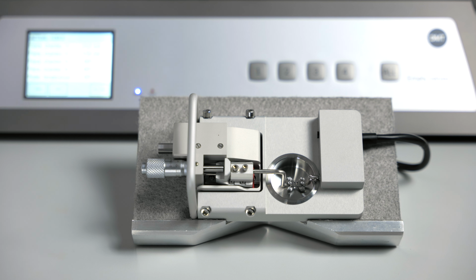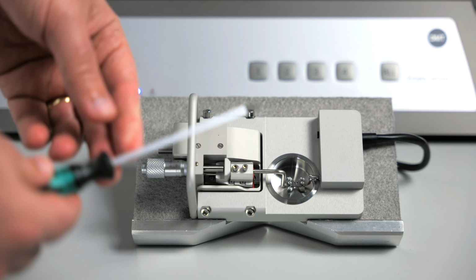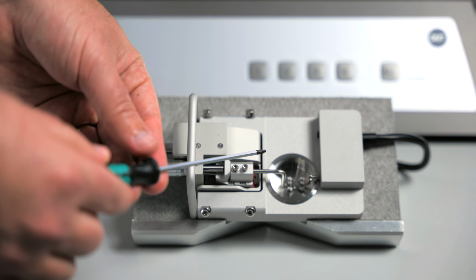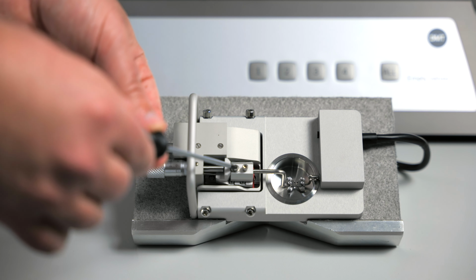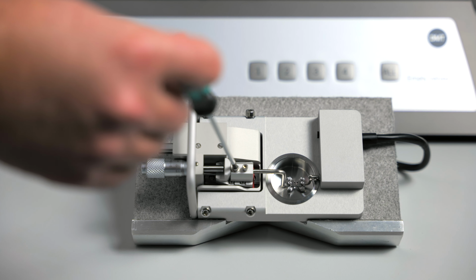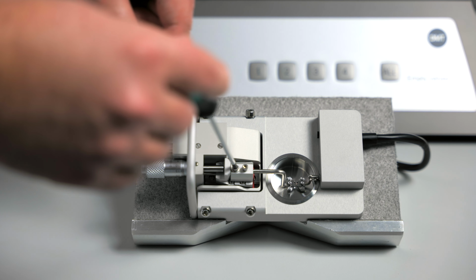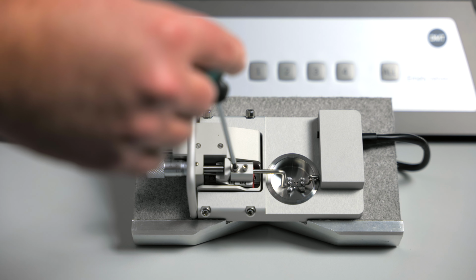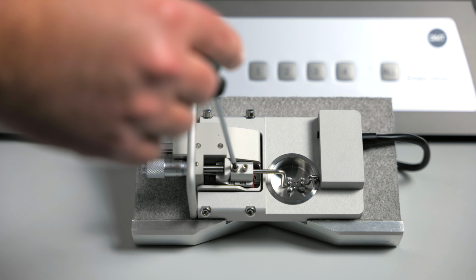In order to adjust the coarse alignment, you will use your ball-end screwdriver and you will loosen the back screw, not the screw used before. This will allow you to drastically move the positioner side mount in many directions. You will use this to get as close as possible to the transducer side.